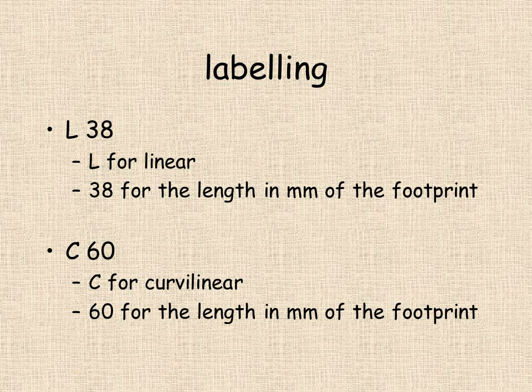Ultrasound probes are labeled using a combination of letters and numbers, such that an L38 probe is a linear probe depicted by the L, and this has a 38mm footprint when applied to the patient. A C60 is a curvilinear probe, which in this case has a footprint of 60mm, which would be most unsuitable for superficial scanning in the neck, because it's designed to look too deep and will be unwieldy when placed against the neck.